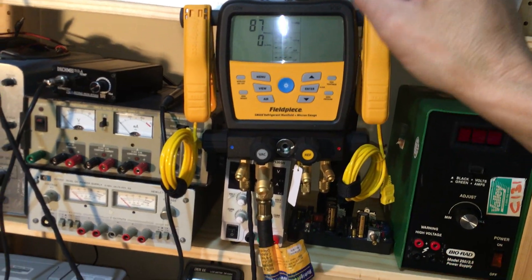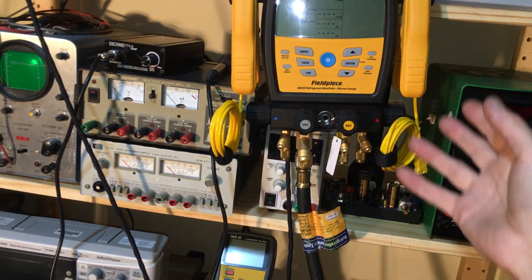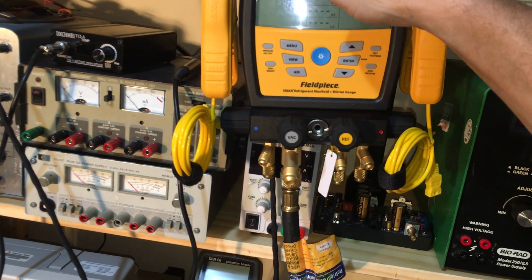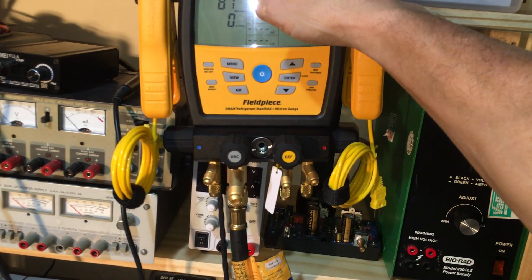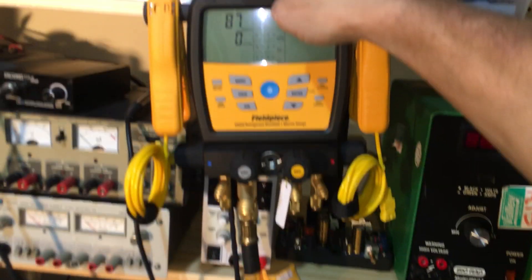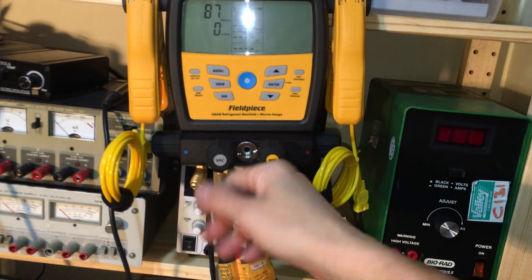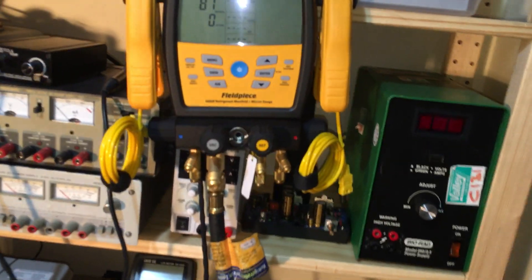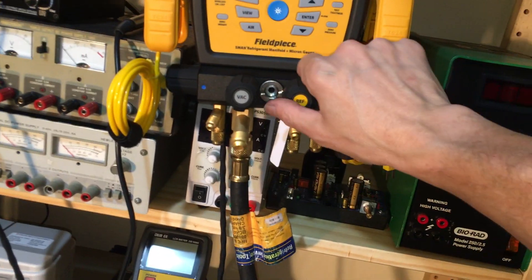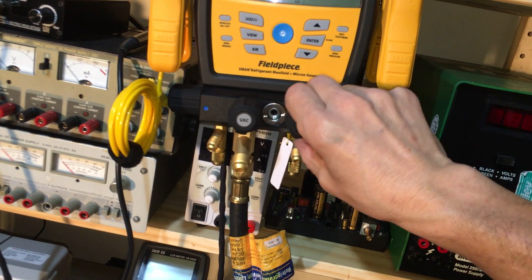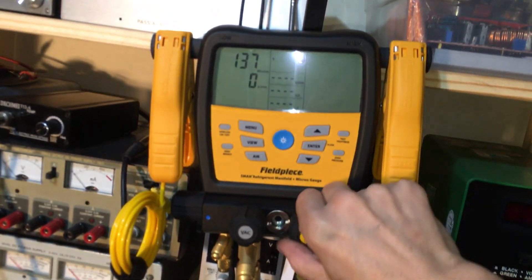Before I went to bed last night, about midnight, I turned the vacuum pump on again and just let it run all night. When I came this morning, it was like 67 microns. I turned it off. As you can see, it's a couple hours later after being at 67 microns, we've raised to 87 microns. Then I proceeded to play with the valving, started opening and closing.